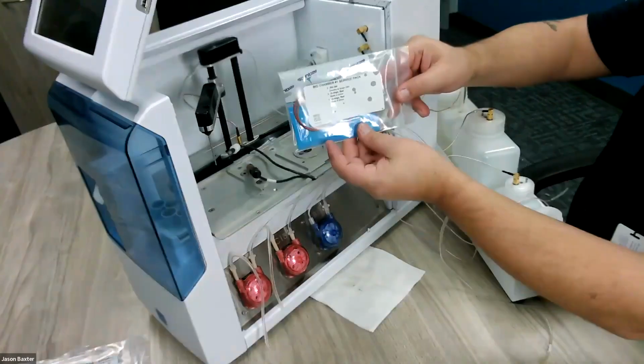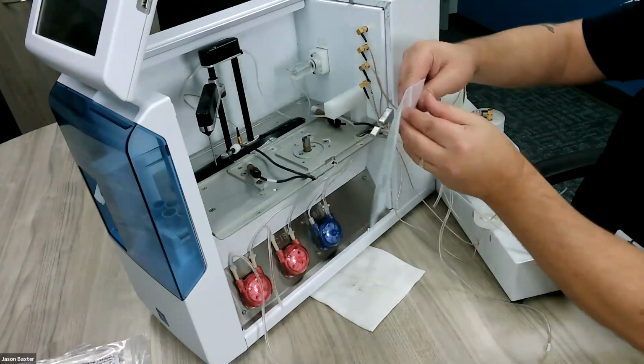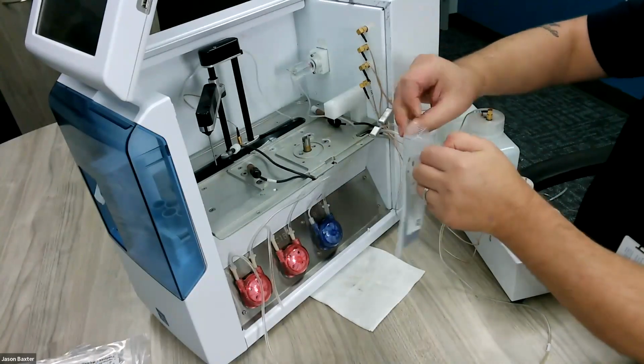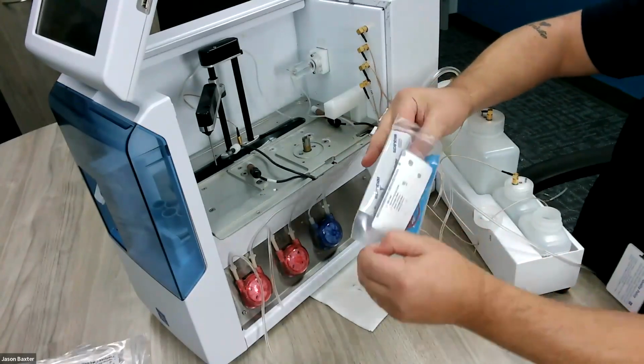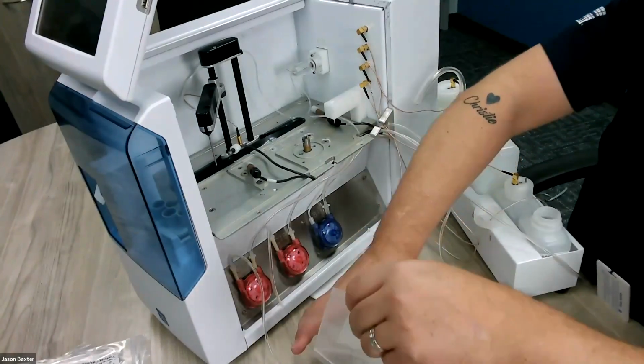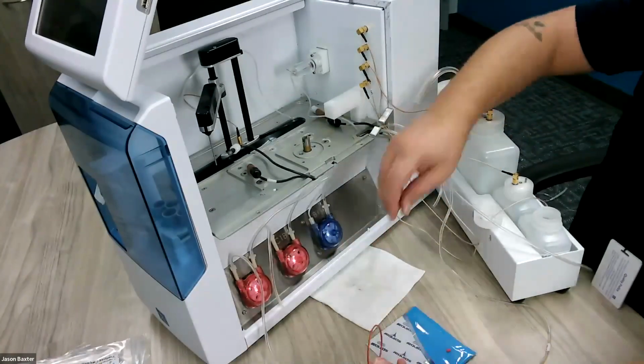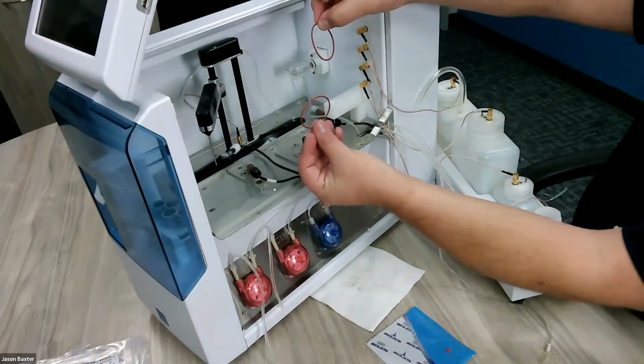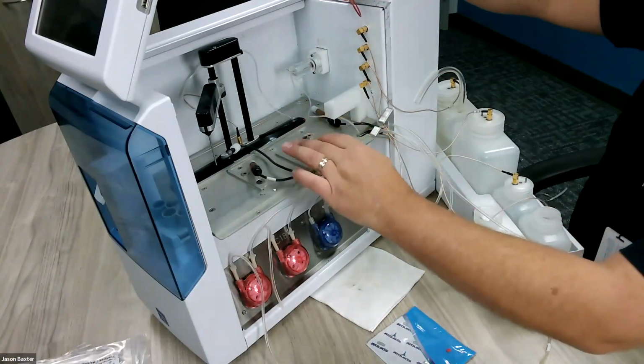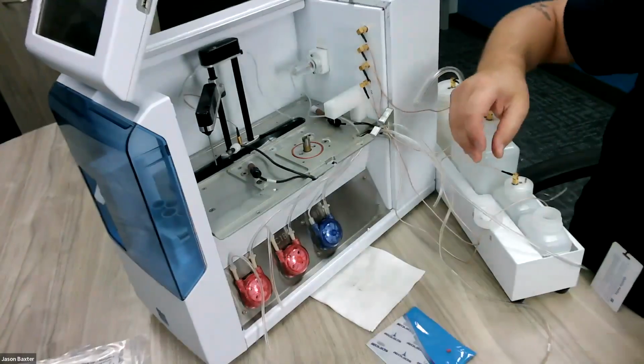Moving on, we're going to go to the BioChamber #1 service pack. This pack has 3 O-rings and 2 stir bars. We give you 2 stir bars. That way, in case you lose one, you've got a spare. The 2 large O-rings are the same diameter. One large O-ring goes down onto the deck.